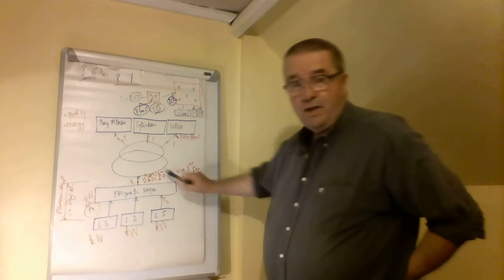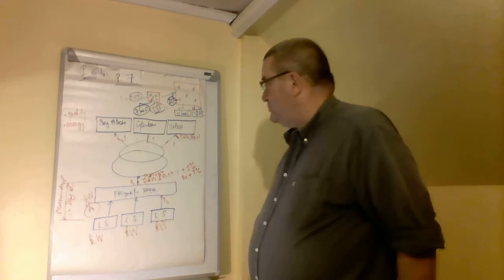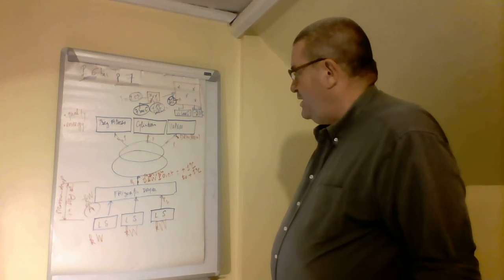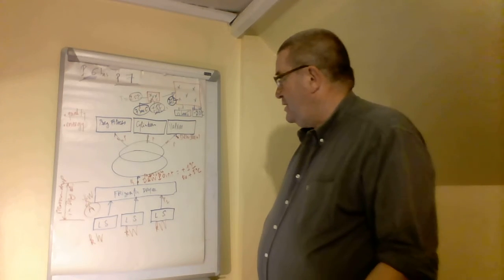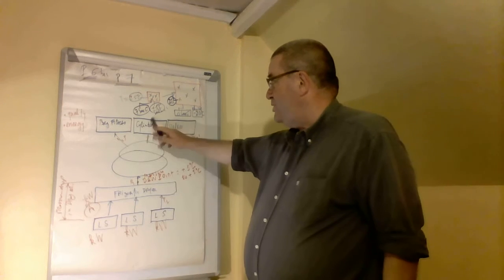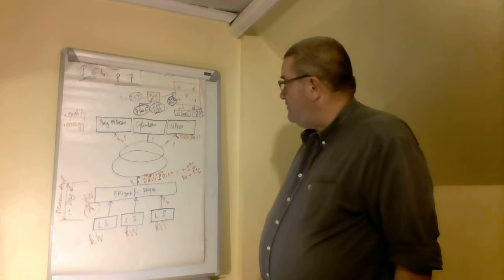You have to see if the pipework is going outside or not, or in a cold room, you know, in some meat industry you have cold rooms, and then you have to check if the way you use air on pneumatic engines produces or not low temperature at the outlet, in which case you may have to put here a special dryer, okay?